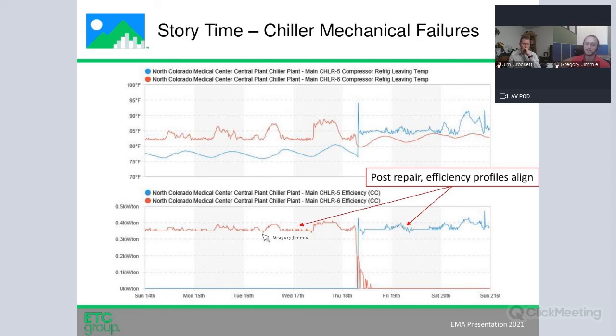And this is just great to see, because as one chiller staged off, the next one staged on, you kept that same efficiency profile. Also, the discharge refrigerant temperature now comes much more in line. We're no longer seeing that 100 or 105 degree leaving temperature. So that was just a really cool, clear-cut problem, solution, and then obvious result and savings from fixing that.